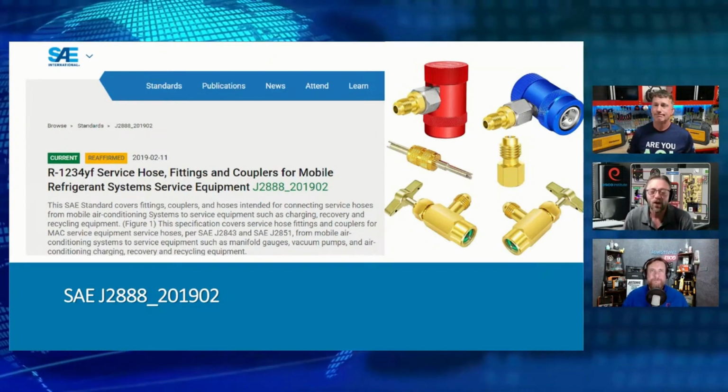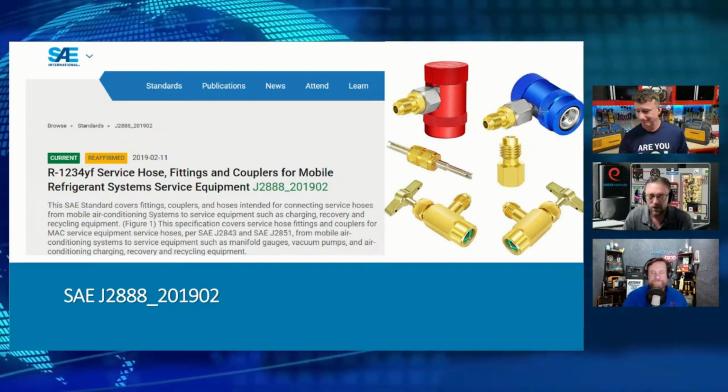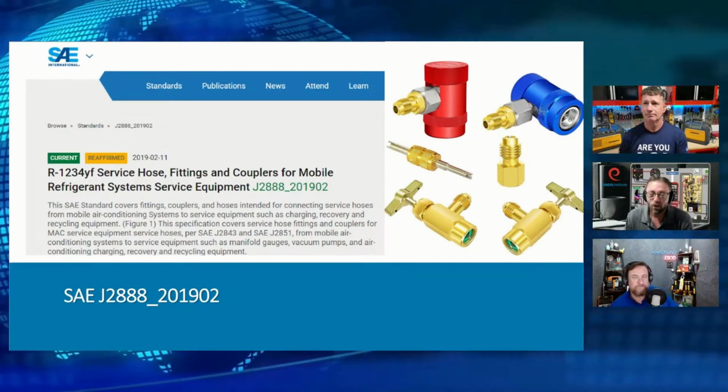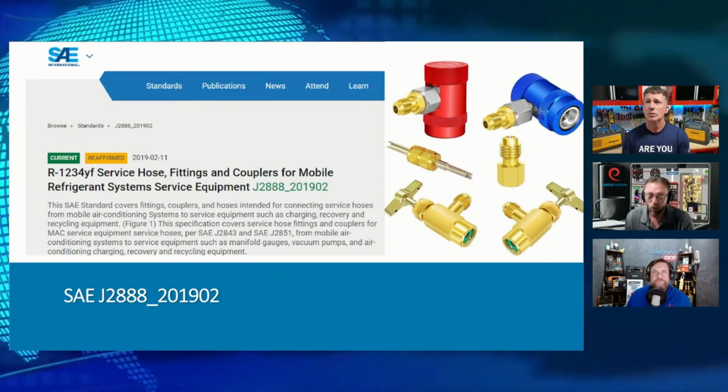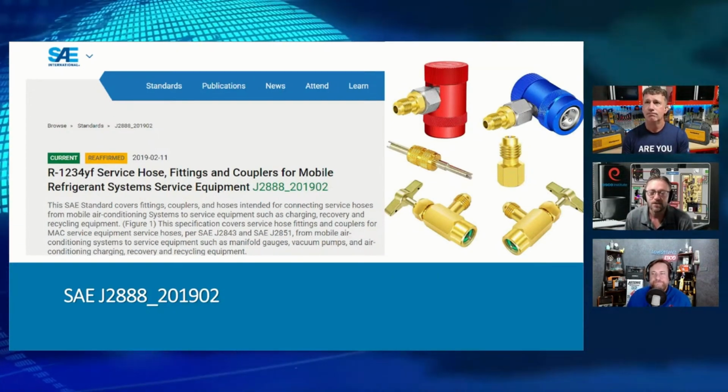So when I say the word flammable refrigerant, you think, well, I can't use the torch. But when you're pulling the torch out, the system is empty, and we should be purging nitrogen. So we're okay to go there. Yes, you can braze these systems.